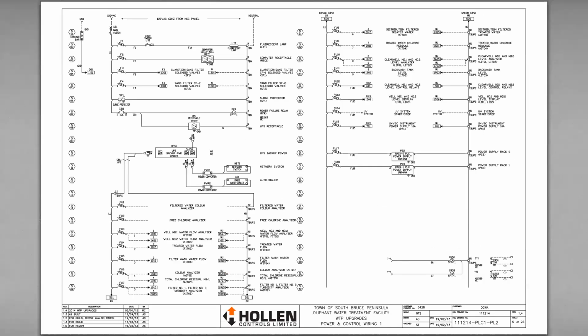Sorry, I'm going back more. If there are any questions while I'm doing this, please stop me. So again, more fuses showing we were powering up the different instruments. Here on FU17, we've got the PLC rack 0 power supply, and on fuse 18, that's PLC rack 2 power supply. Those are our 2 CompactLogix racks. Each one requires its own power supply.